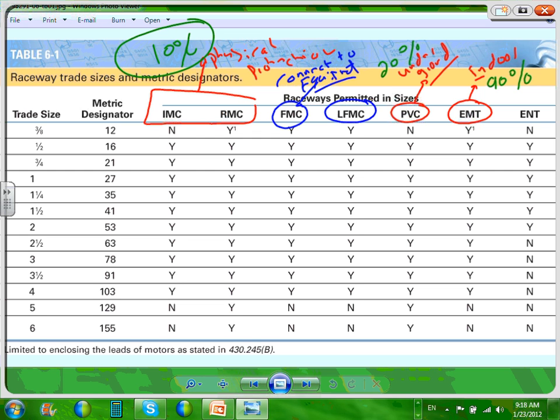Now, who's going to tell me what the heck is this liquid tight flexible metallic conduit? Same as tied to equipment. The only difference with this one is wet and this is dry. Does that make sense? The major difference between these two conduits is the word wet, dry. Take this. I have an air conditioning, guys, well, a rooftop unit on the roof. Is this a wet location? On the roof, tying to it? Yep. It could rain and snow in Minnesota and everywhere else. Then when I tie to this equipment, what's my conduit of choice? To tie to the equipment, liquid tight flexible metallic conduit.